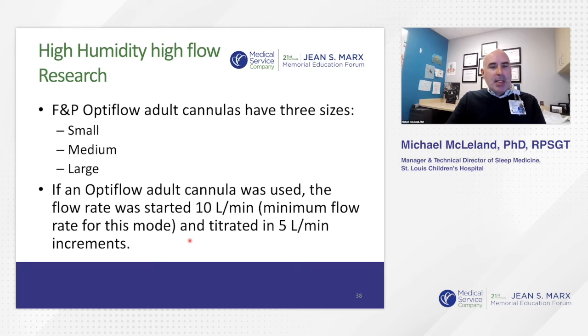If they were using adult cannulas, there are three sizes: small, medium, and large. The AirVo will only let us start at 10 liters per minute for adult cannulas. So if it was a pediatric patient wearing a small adult cannula, we would start at 10 liters per minute, but we would still increase only in 5 liter per minute increments.